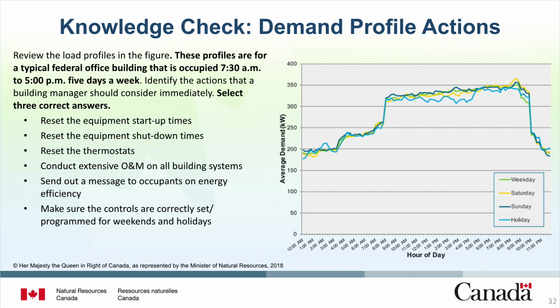The following are the correct answers. Reset the equipment startup times. This is a first step toward achieving optimum building performance. Reset the equipment shutdown times. This is another first step towards achieving optimum building performance. And make sure the controls are correctly set and programmed for weekends and holidays. Make sure the equipment schedules are correct for days when the building is not scheduled to be occupied.